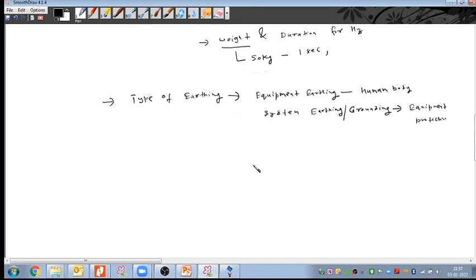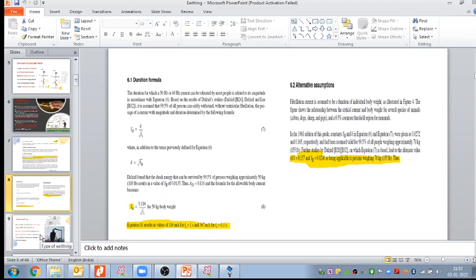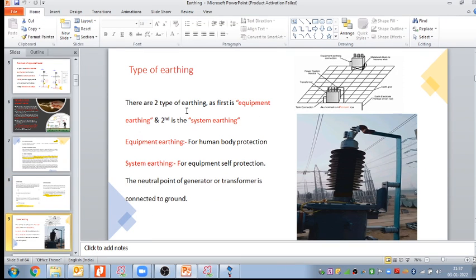So earthing we can divide into two parts. As we discussed in the beginning, if we connect the non-current carrying parts to the earth, then we call it equipment earthing. And if we connect the neutral of the generator or the transformer to the ground, then we call it system earthing or system grounding. So earthing is of two types. This is the conclusion: equipment earthing and system earthing. Equipment earthing is for human body protection, system earthing is for equipment protection. The neutral point of the generator or transformer is connected to the ground. This is the meaning of system earthing.